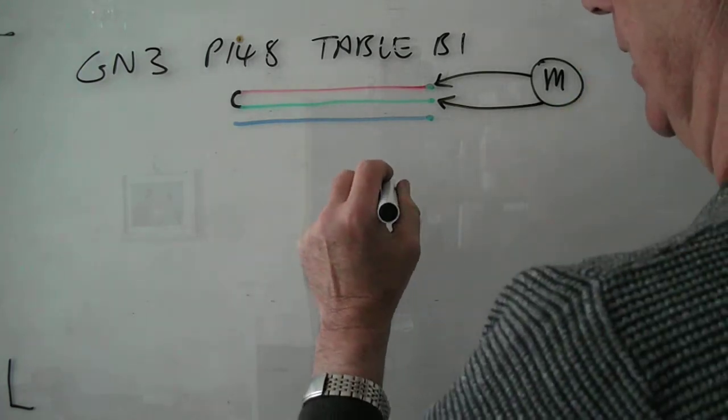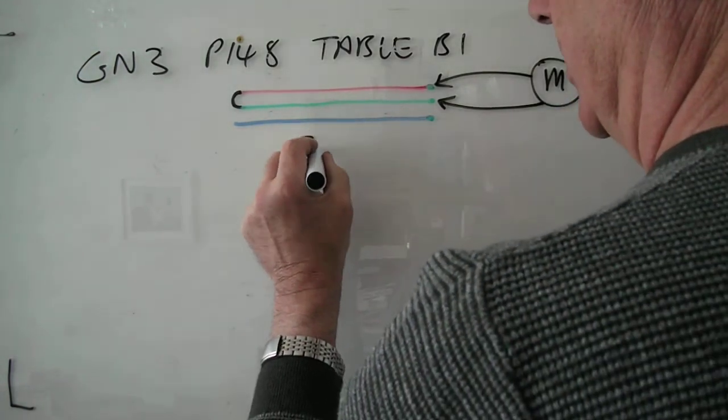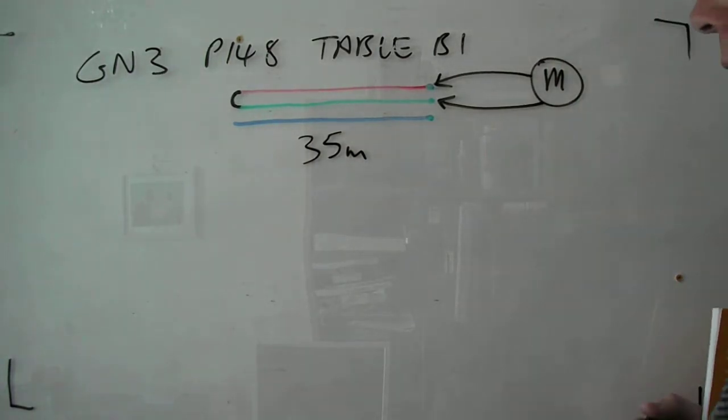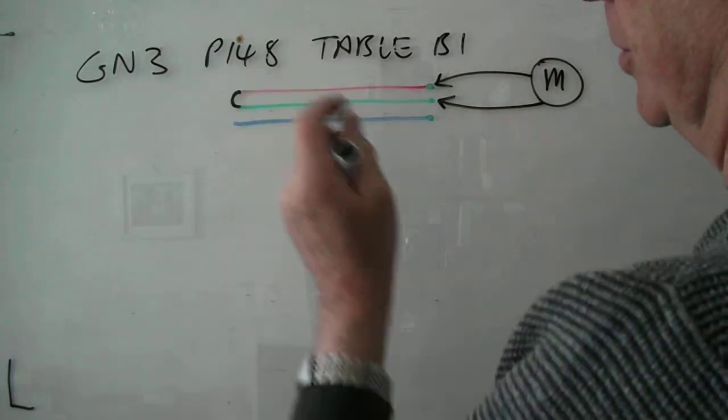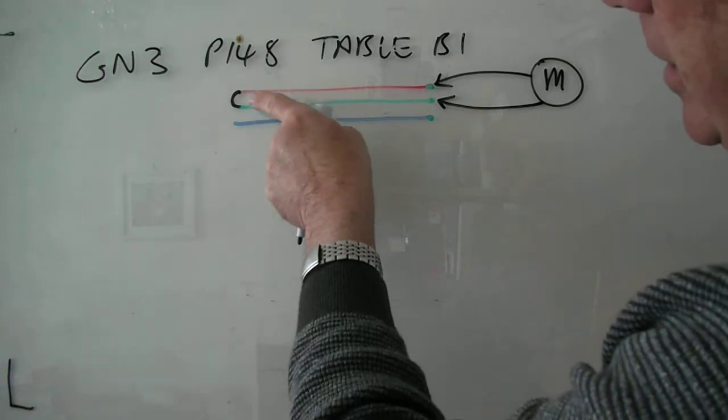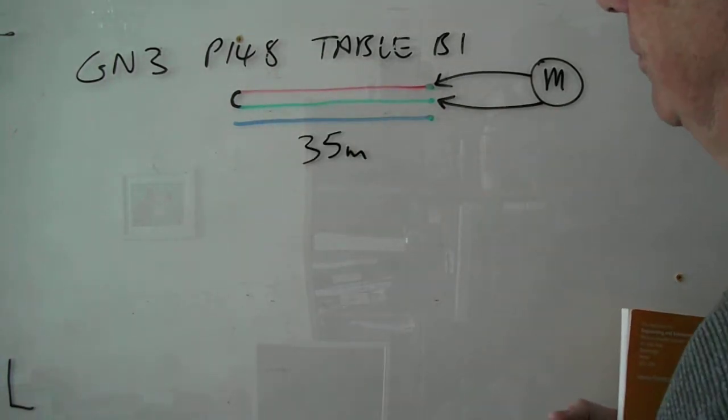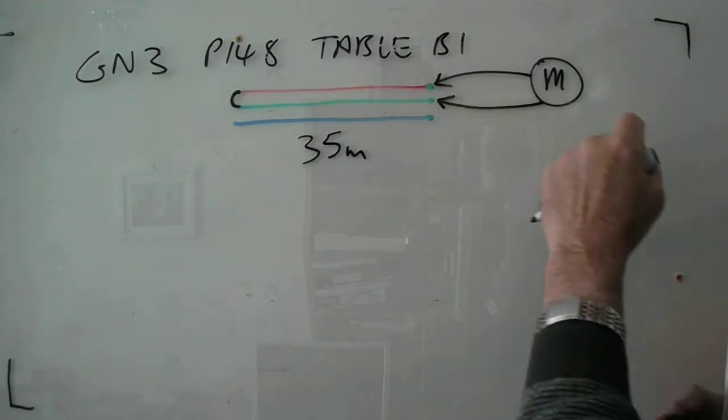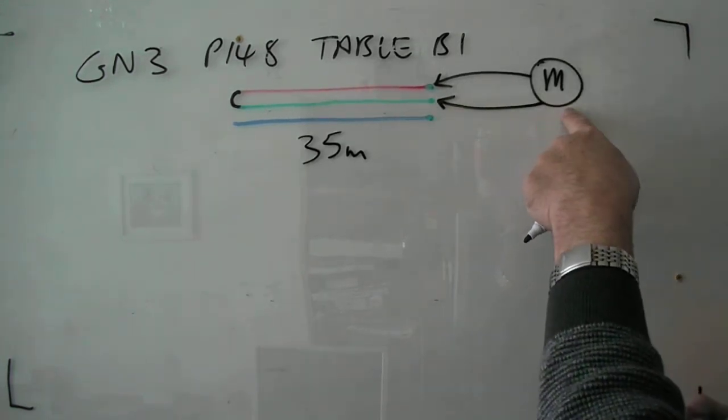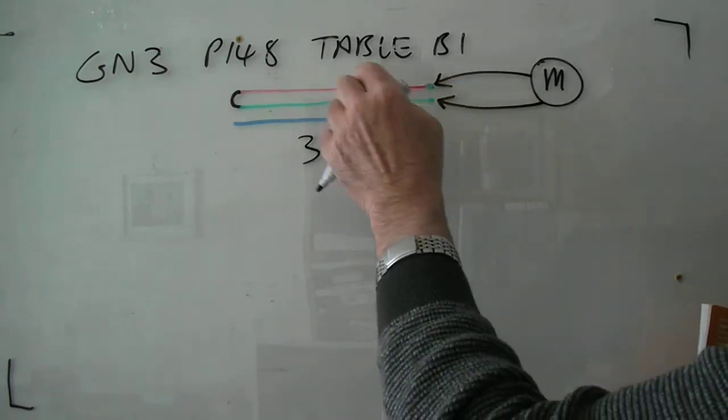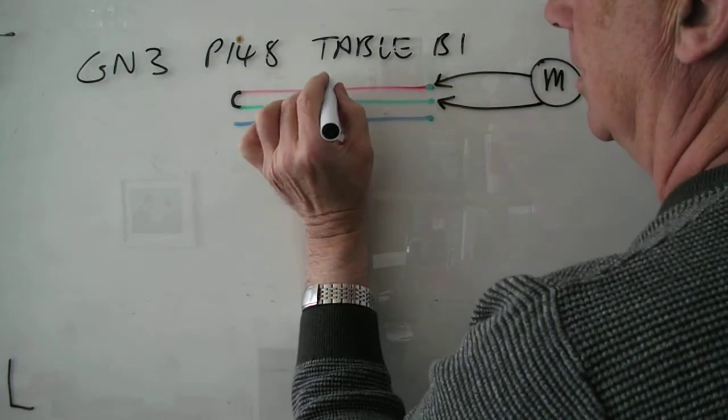Let's say the twin and earth cable is 35 metres long and what you've done is you've shorted out the link between earth and live at the distribution board for that circuit and you go to the other end of the circuit with your megger and you're measuring the resistance between what we call R1.